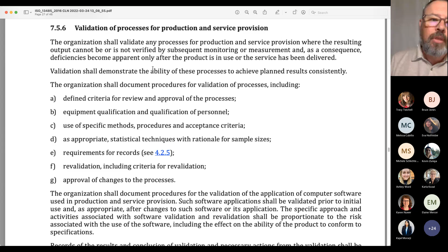The organization shall validate any process where the resulting output is not going to be verified. And if you look at the FDA language in this regard, it uses the phrase fully verified. So essentially, if you're not capable or not planning to 100% verify a CTQ or a functional aspect of a device, then you have to validate your manufacturing process as it pertains to that particular criteria. You have to show through validation that the process can produce outputs that are consistent, defined usually in the context of capability, okay? And you're going to have procedures for the validation of processes or process validations that includes the following.